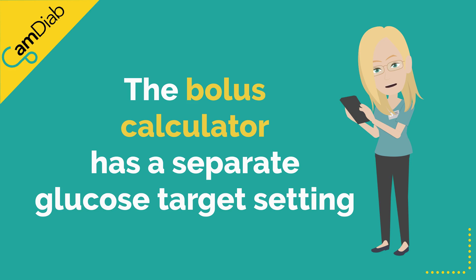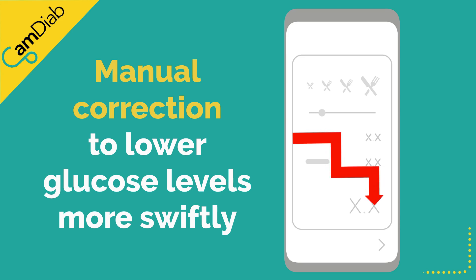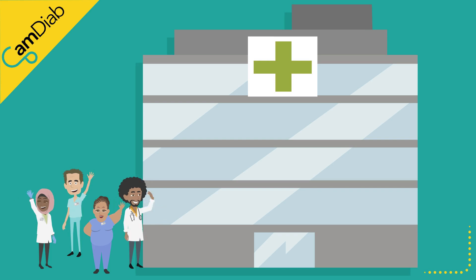The bolus calculator has a separate glucose target setting. This target is only used when someone asks for a manual correction to be given via the bolus calculator to lower high glucose levels more swiftly. Please program both these glucose target settings with the support of your diabetes team.